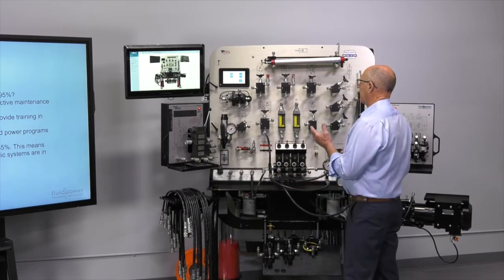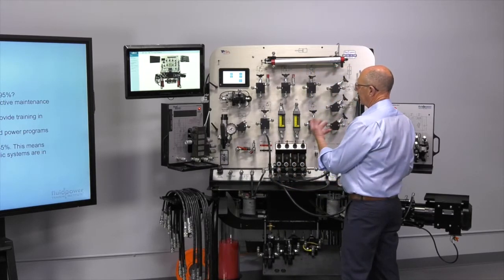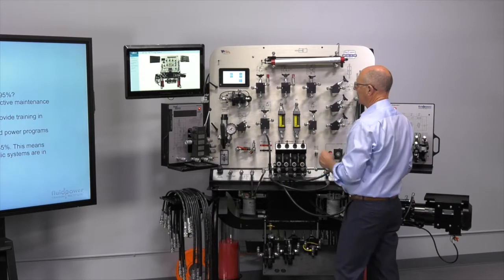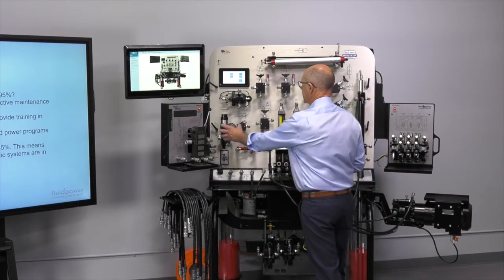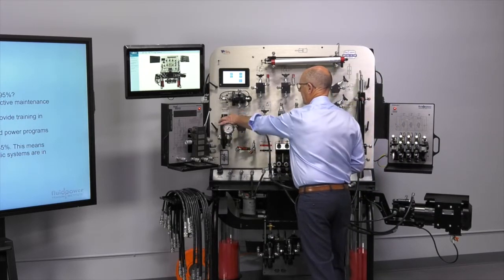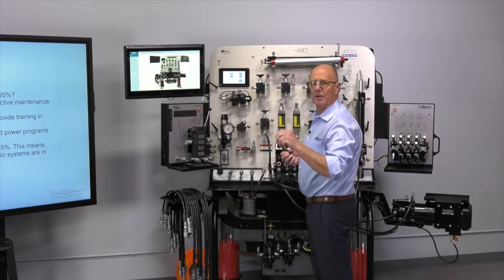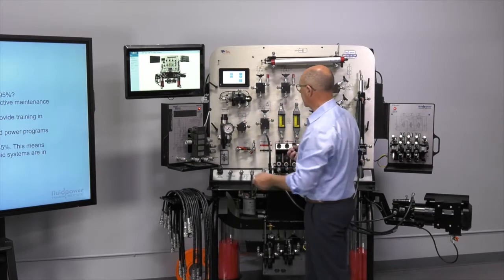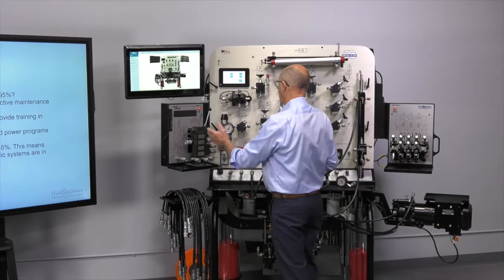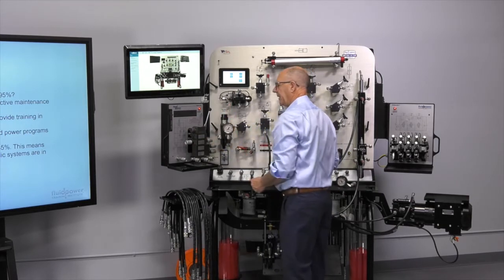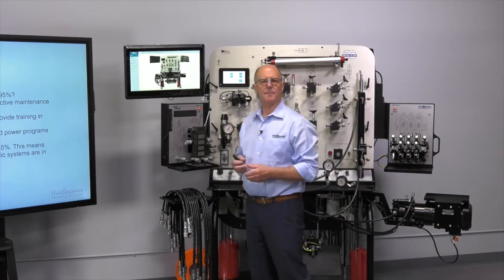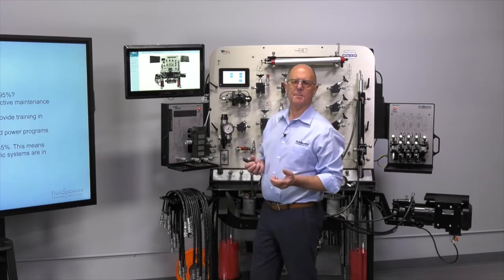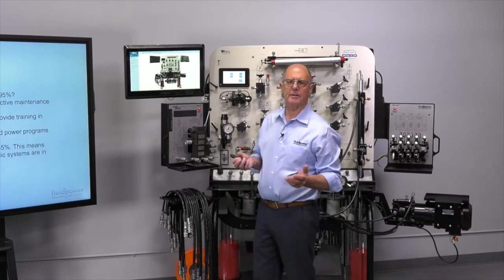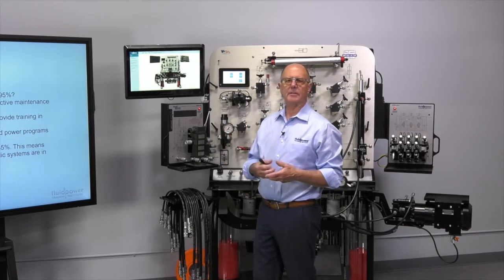The microleak test system here is very simple and straightforward. It's a little pump with a knob on it — you open and close it to generate pressure, and then you just pump to operate the device. Very simple, very straightforward. Imagine you're in the field — a little pump is all you need.